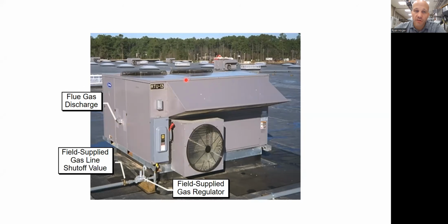In this case, there are a couple other things on here we might as well point out while we're here. There's a disconnect on here. This is an external disconnect. You could have a disconnect inside the unit. I don't really like that. I like it to be external. So when you go to change this unit in 15 years, you can just disconnect it from the disconnect and leave the disconnect sitting there for the next unit ready to go. But there's a disconnect here electrically, so you can shut it off while you're working on it. There's a gas valve you can shut off while you're working on it.